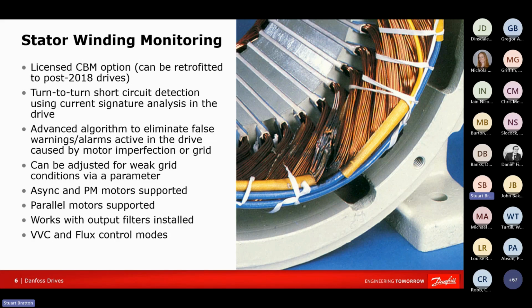So our licensed CBM features include a number of functions. The first of which is something we call stator winding monitoring. This uses current signature analysis, like a frequency spectrum analysis of the current going out to the motor, and it's able to detect a change in that current signature. It's so advanced that you can actually detect a short circuit between two adjacent coils in a motor winding.